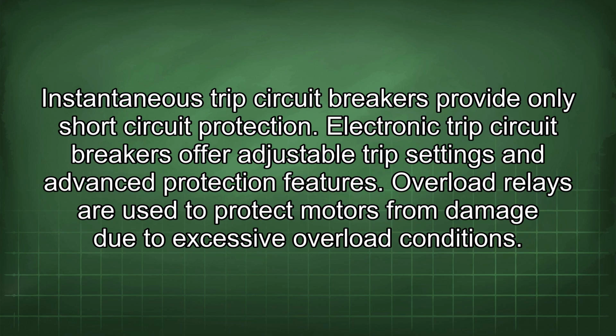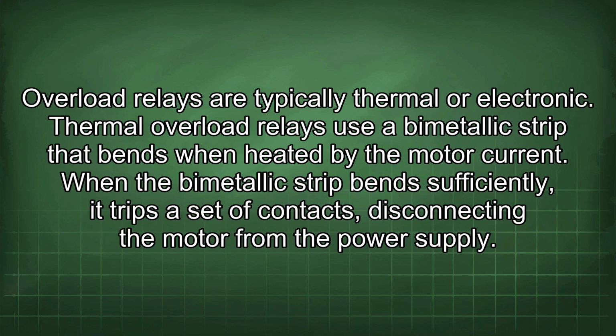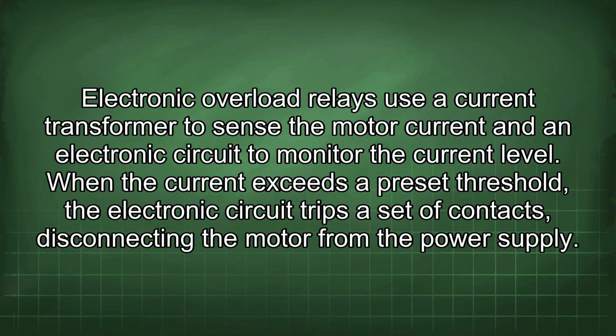Overload relays are used to protect motors from damage due to excessive overload conditions. Overload relays are typically thermal or electronic. Thermal overload relays use a bimetallic strip that bends when heated by the motor current. When the bimetallic strip bends sufficiently, it trips a set of contacts, disconnecting the motor from the power supply. Electronic overload relays use a current transformer to sense the motor current and an electronic circuit to monitor the current level. When the current exceeds a preset threshold, the electronic circuit trips a set of contacts, disconnecting the motor from the power supply.